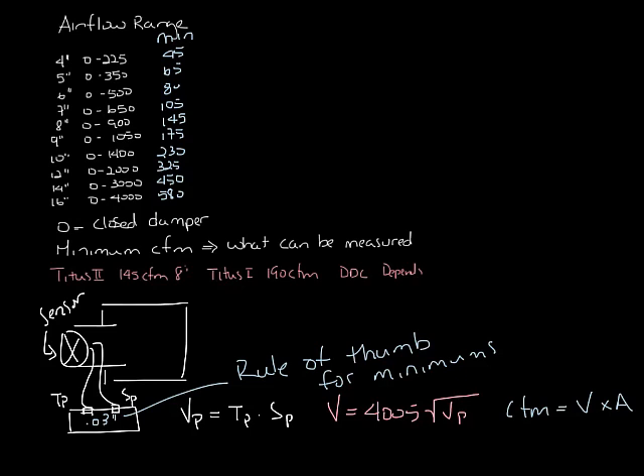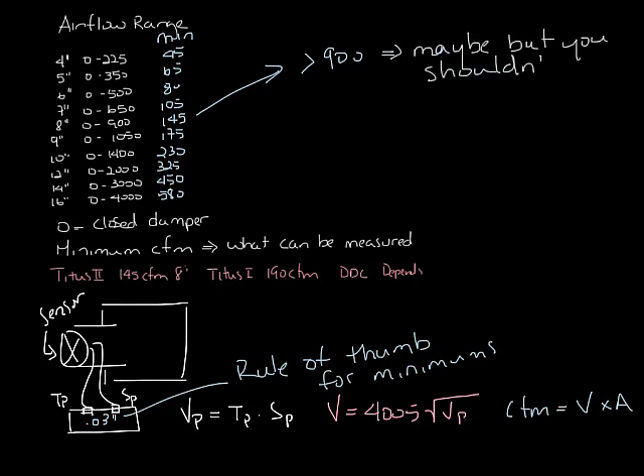So now let's look at the maximum number. Obviously you could force a lot more air through an 8-inch VAV box than 900 CFM, but like they say, just because you can do it doesn't mean you should. Ideally, you'll want to keep the velocity through the inlet around 2,000 or 2,200 feet per minute.